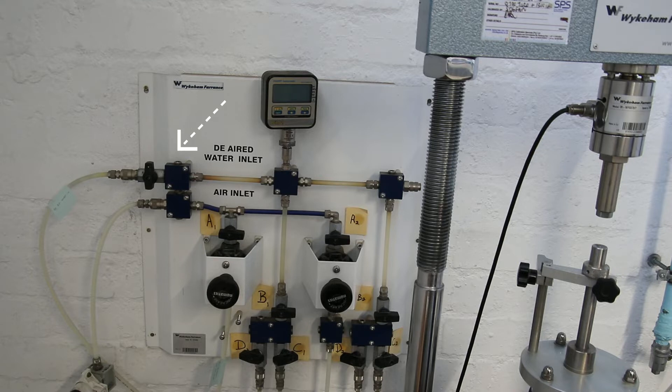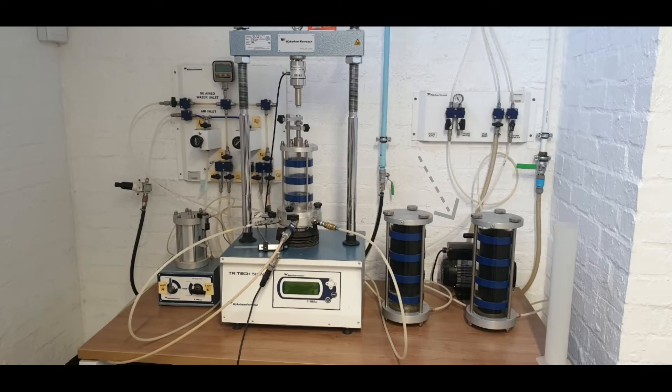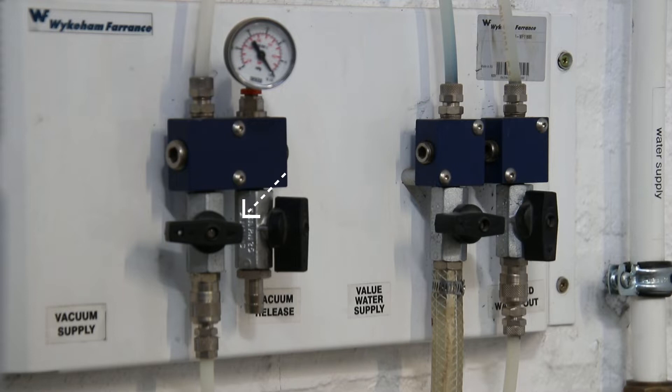Open the valve labeled 'vacuum supply.' Close the valve labeled 'vacuum release.' Turn on the vacuum pump, let it run to full vacuum, and let it run for 10 to 15 minutes. After 15 minutes, turn the vacuum pump off.